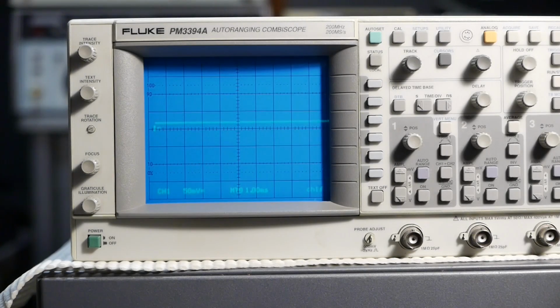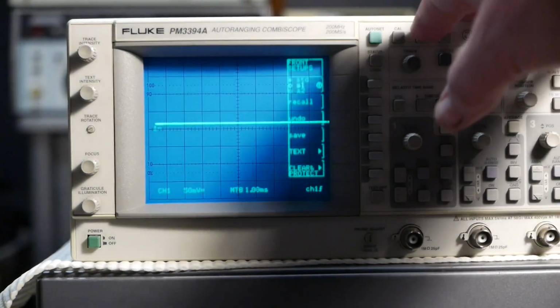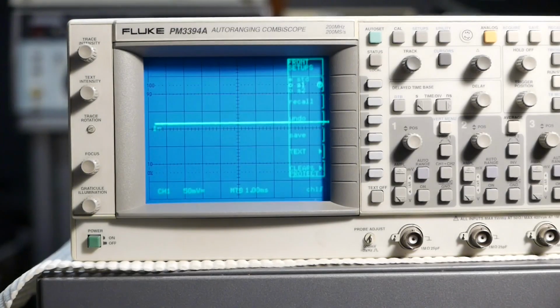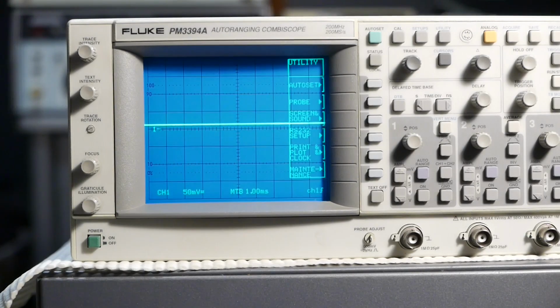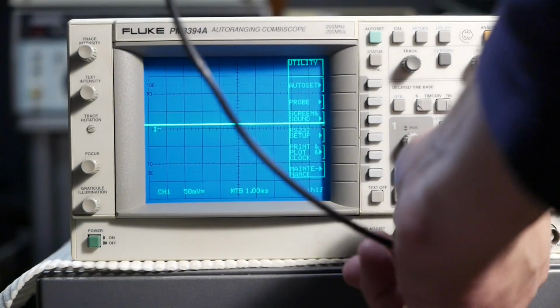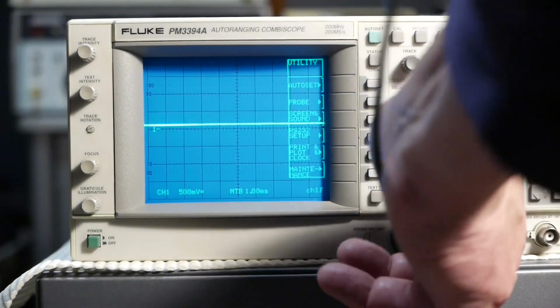This particular one has a couple of faults. One is really minor, the backlight illuminator isn't working, and I'll fix that. But the other one's more concerning. What I'm seeing on the CRT is a pulsing or glitching - the display is contracting and then stretching out. It's pulsing at a slow frequency that is proportional to the brightness of the display, which in effect is proportional to the CRT beam current.